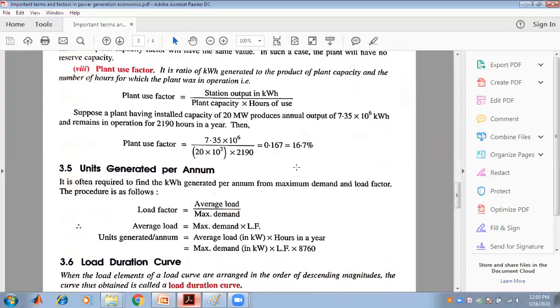Another important quantity is units generated per annum. Since load factor equals average demand divided by maximum demand, the average load equals maximum demand multiplied by load factor. Therefore, units generated per annum equals average load in kW multiplied by hours in a year, which is maximum demand (kW) multiplied by load factor multiplied by 8,760.